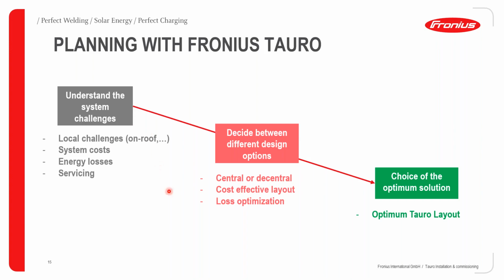Then once you understand your system challenges, it's time to decide between different design options. Are you going to go for a centralized or a decentralized design? What is the most cost-effective layout that you want to use? And this most cost-effective layout must also address the loss optimization. You want to minimize your system losses as much as possible. And this therefore leads us to the choice of the optimum solution. And the choice of the optimum solution will also depend on: is it a ground-mounted system? Is it a roof-mounted system? Will I go for centralized or decentralized, or will I go for a combination of centralized and decentralized topologies? And the Tauro, because of the design flexibility that it's giving us, is going to allow us to have an optimum layout, which we are going to look at.